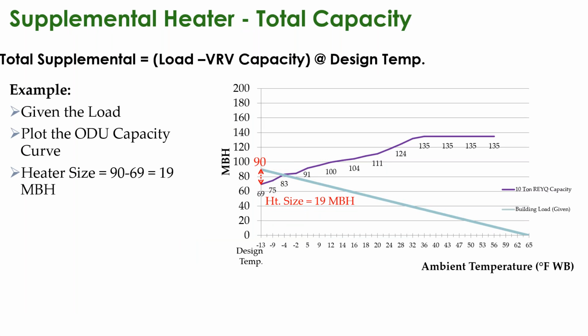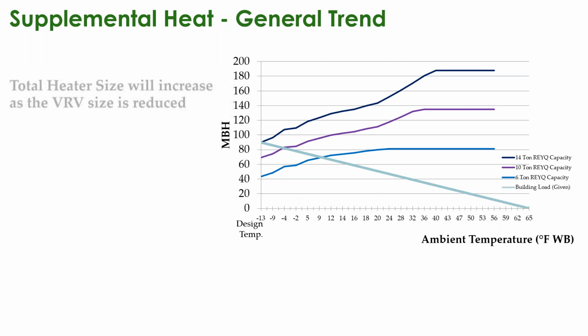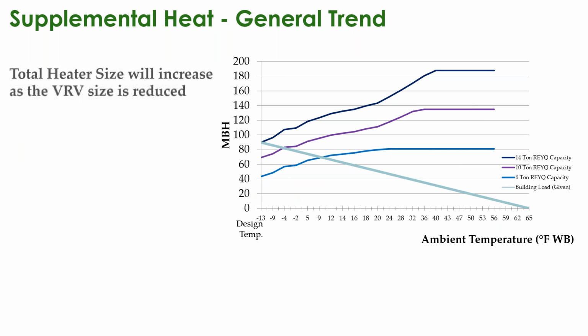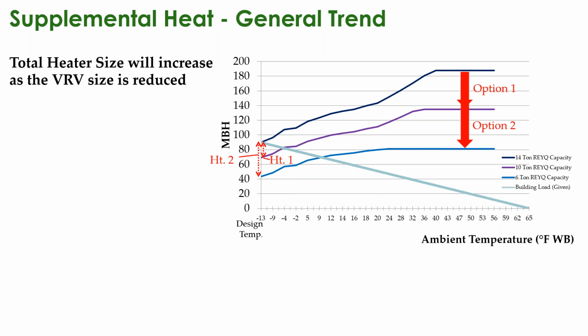So given the load in this case, we're saying that this load is 90,000 BTUs at minus 13. We're looking at this with a 10-ton nominal capacity outdoor unit. Your difference, or your heater size total requirement in this example, is going to be about 19,000 BTUs or approximately 6 kW total heater size. And this is where, again, you have to look at whether the juice is worth the squeeze. Is it better to have a larger condensing unit to reduce your heater size, or is it better to increase your heater size to reduce the variable refrigerant system sizing?